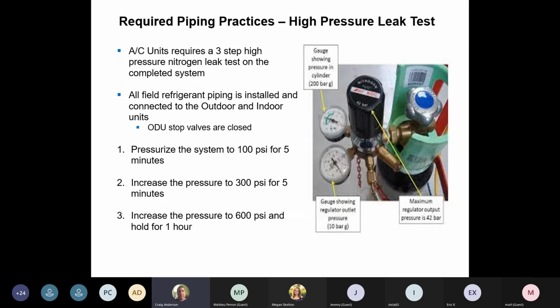These units can operate up to 500 PSI before the actual compressor will go out on an internal overload or a high pressure. The compressor will shut off, but they can get up to this pressure. So let's test it at that pressure. Let's make sure it can run at that pressure and we have no leaks. So do a 3-step, save yourself some nitrogen, 100 PSI for 5 minutes, and then boost it up to 600 PSI and hold it there for an hour.